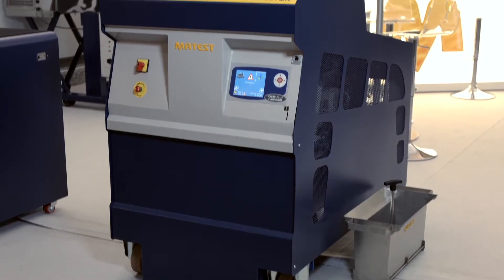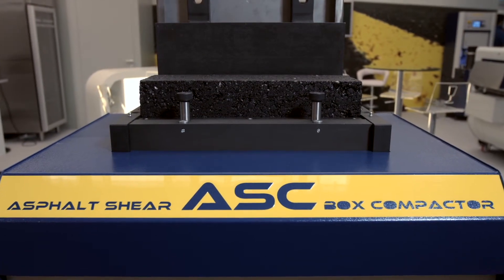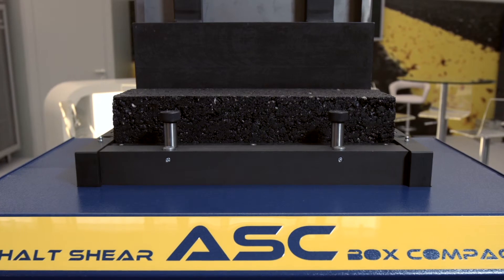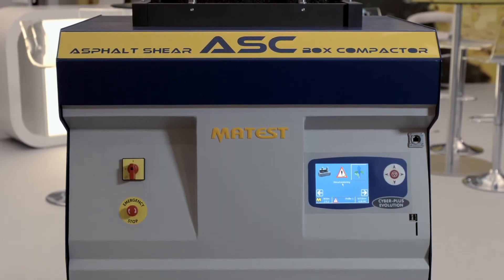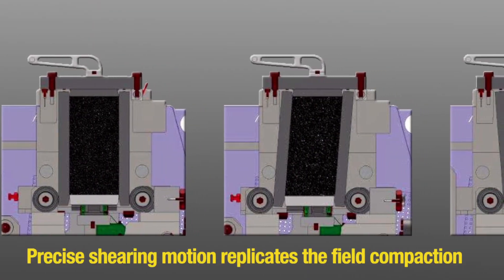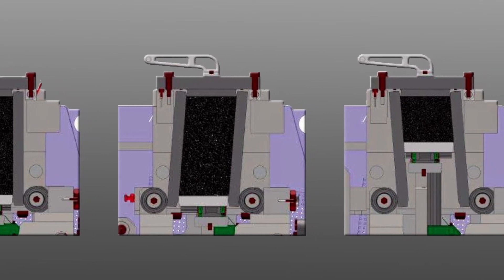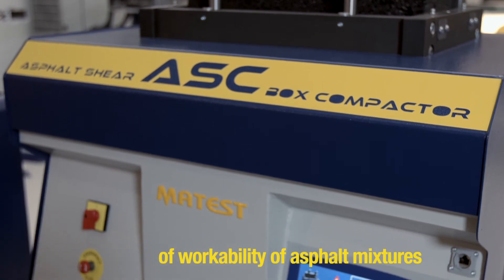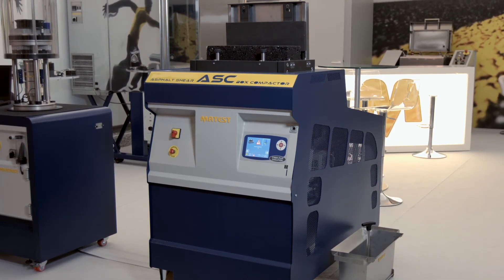The asphalt shear box compactor, or ASC, compacts large asphalt prisms 150mm wide by 450mm long at the precise height specified by the operator, up to 185mm. The prisms may be cored to yield three or four AMPT specimens or cut into four to six beams for four-point bending tests. The precise shearing motion replicates the conditions of field compaction in order to reproduce the field properties of asphalt quickly and easily under the controlled conditions of a laboratory. The ASC also provides a unique measure of workability of asphalt mixtures, a critical performance-related mix characteristic, and comes with all the necessary accessories for loading and unloading the specimen.